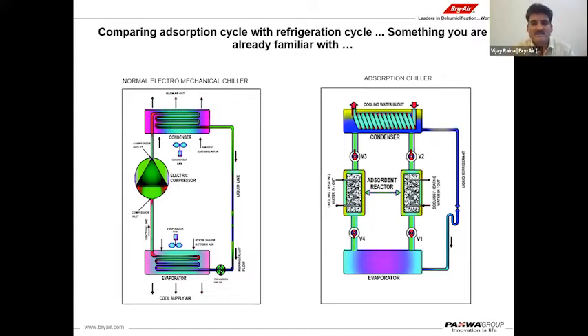So our technology is always water cooled, it is not air cooled, so we always need a cooling tower on the condenser side. So you can see the comparison between the two technologies there. We don't need any compressor, so there is no electrical consumption for our technology. It is nothing but thermally driven, and we use silica gel to transfer energy from outside through our refrigerant water. This is the basic construction of our adsorption chiller.